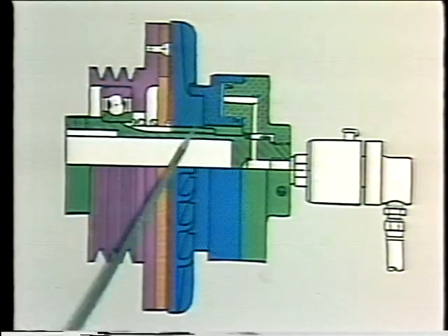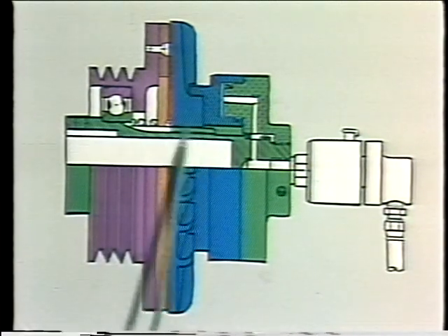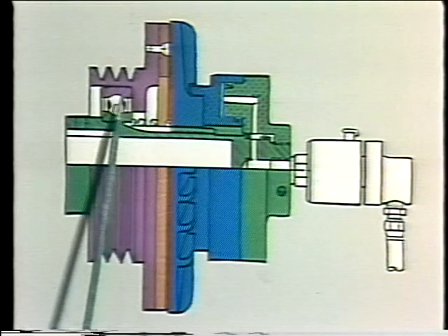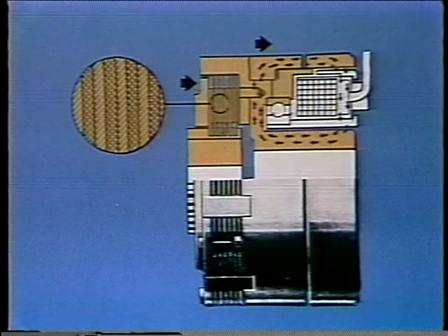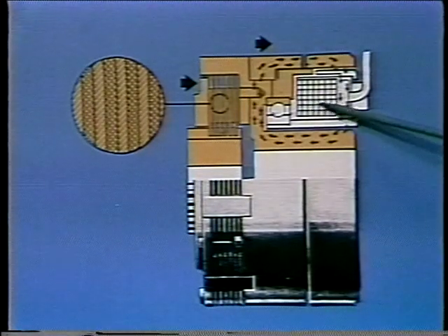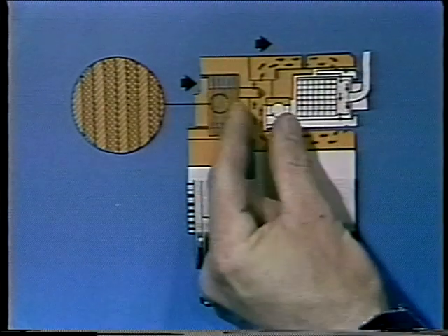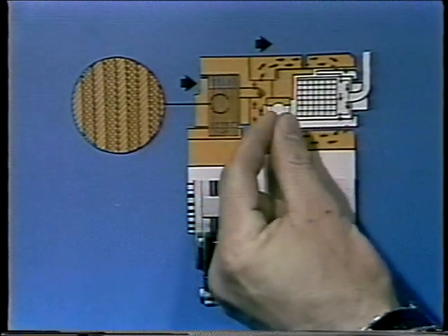This section here with the metal disc is keyed to the shaft, while this purple section with the V-belt pulley turns free on this bearing until the disc is forced against this friction surface. Hydraulic pressure, that is, oil under pressure, could be used as the motivating force just as well. We can use an electric coil, which we've shown here in white, as a magnet, and pull the two surfaces together, as you can see in this sketch.